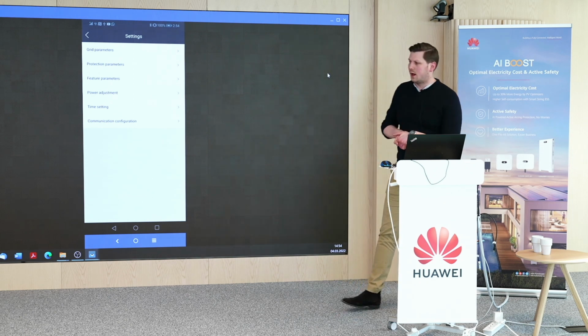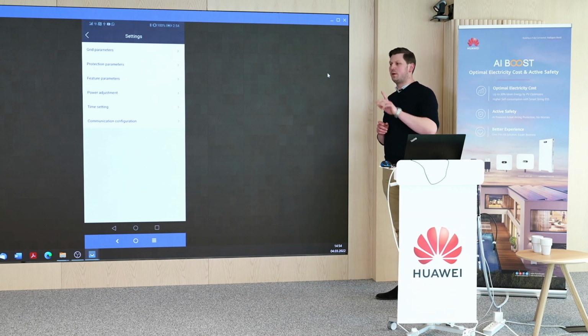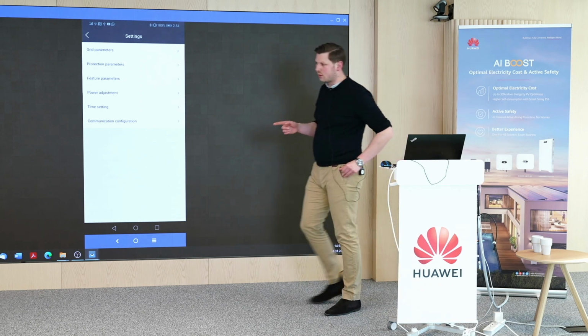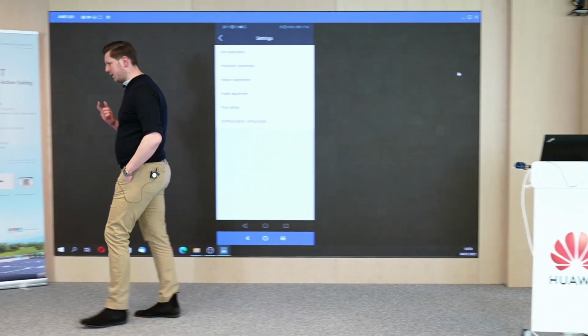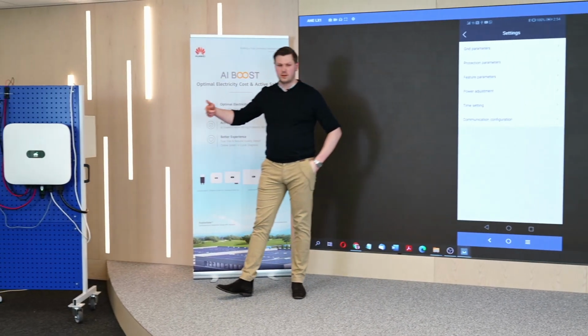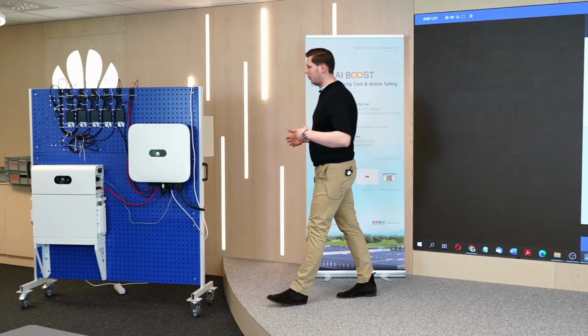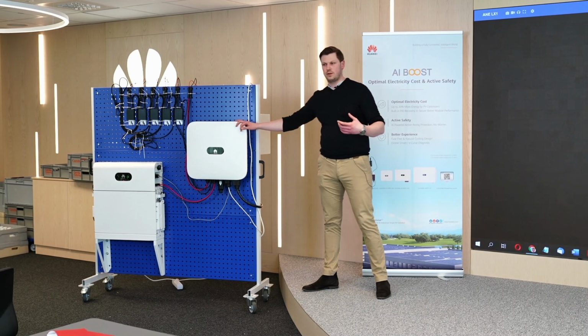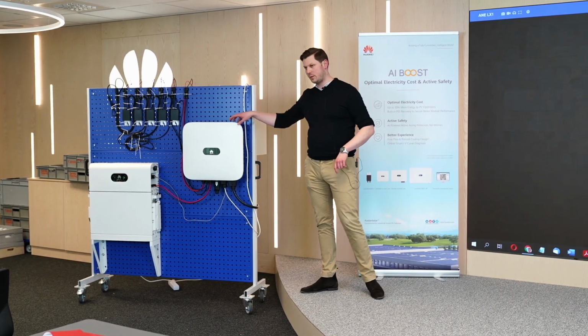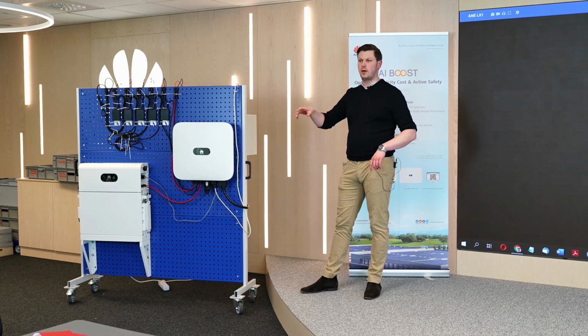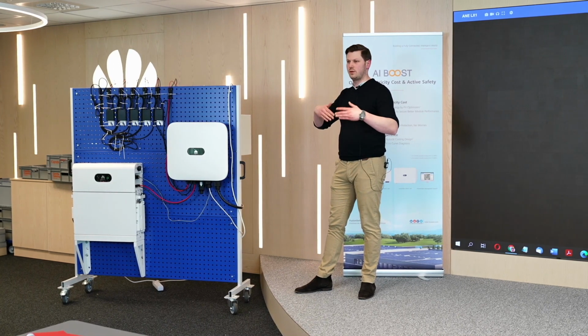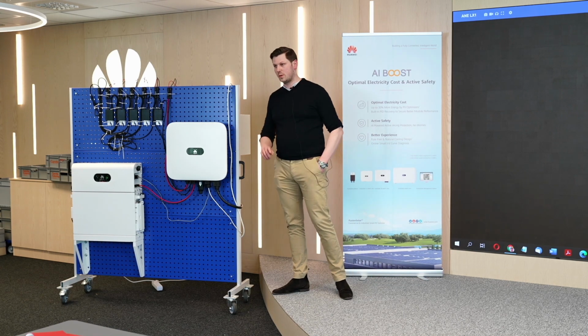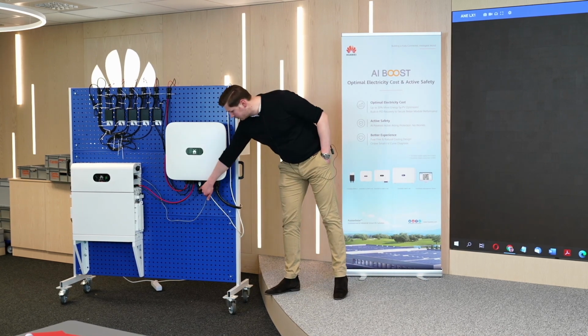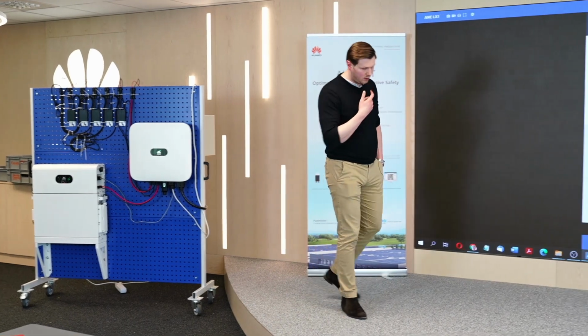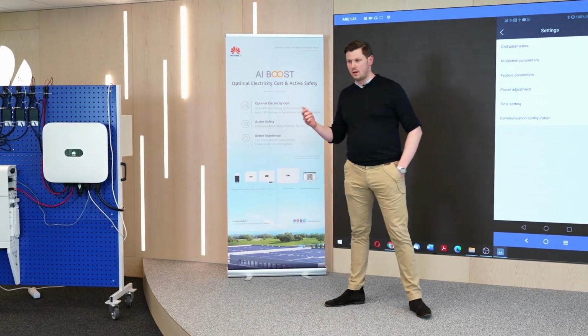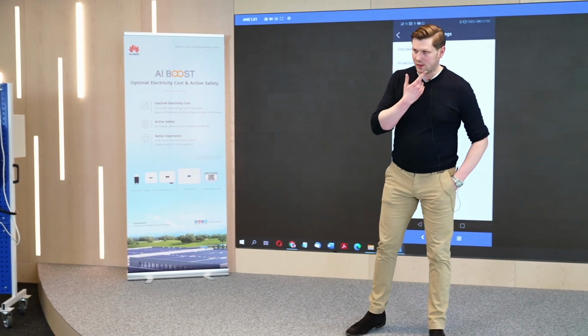Is it through the RS485 protocol? Not exactly. There is this dongle here which is the master for all this communication line, so if you try to read the registers by RS485 directly from the inverter, the dongle stops working because there is a conflict between the master devices. But if you're using Modbus TCP/IP, connected directly to the network device, then it can work at the same time. So this is the way it can be done.